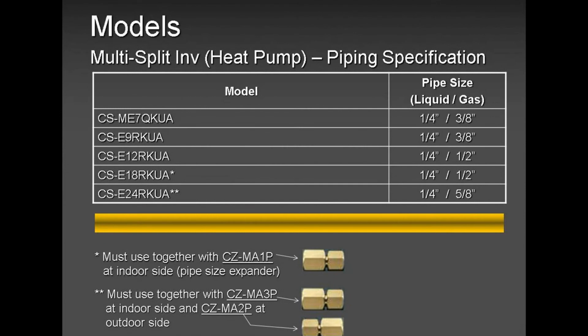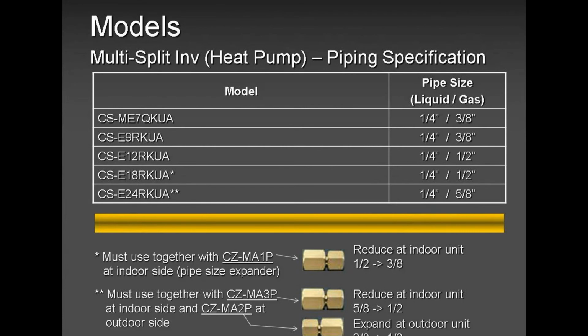Here comes the difference, okay? These are adapters. The adapters that normally be used at the indoor unit. The only time you will use an adapter at the outdoor unit is when you're installing a 24,000 BTU. Guys, listen to this very carefully, guys, okay? When you're installing our multi-zone, regardless, a 2, a 3, a 4, or a 5 zone, the pipe connections at the outdoor unit are all 1/4 and 3/8. Unlike Mitsubishi, Daikin, and other companies, they have different sizes. With us, all sizes at the outdoor unit is 1/4 and 3/8.